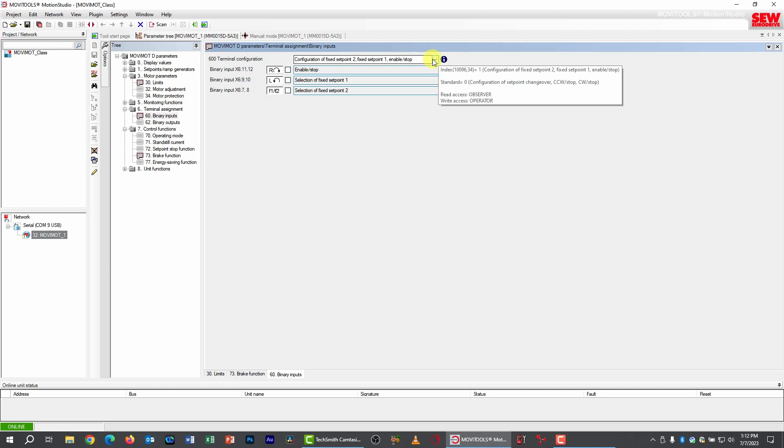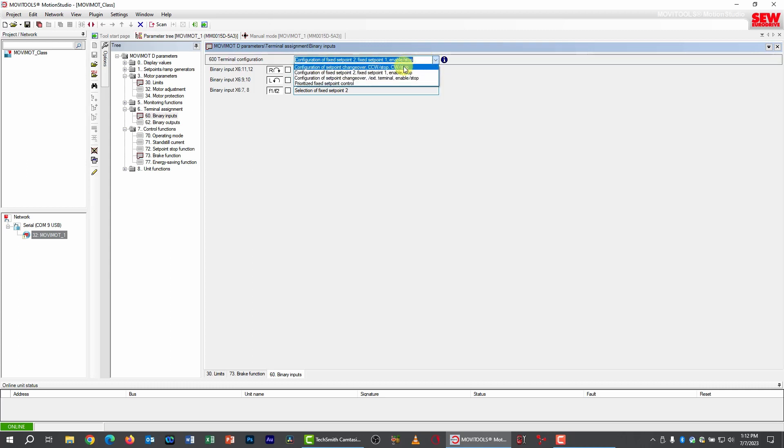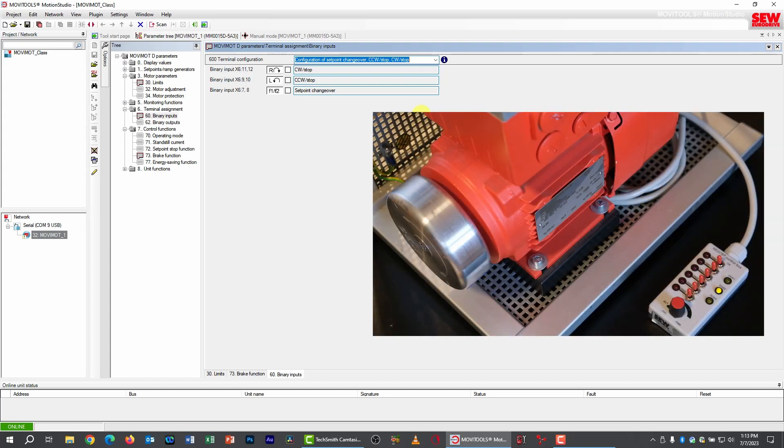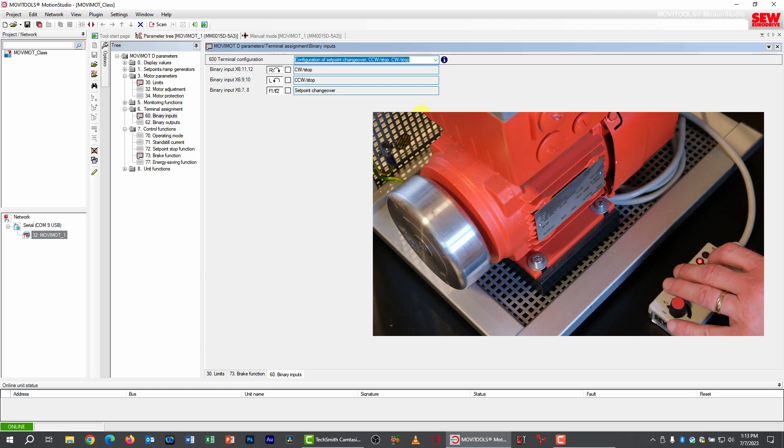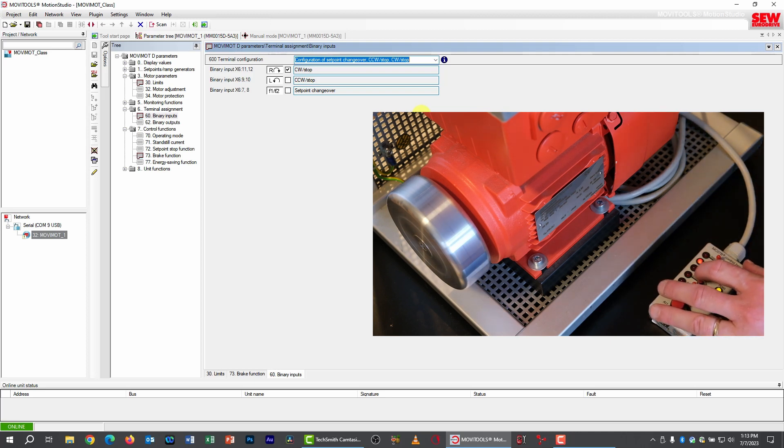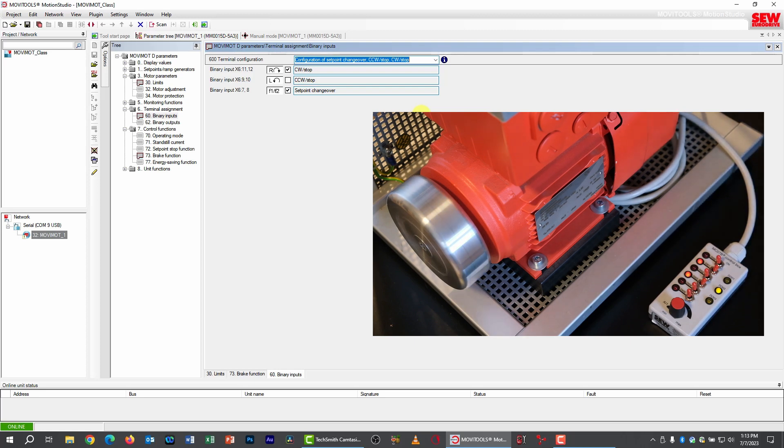And we need to go back to the standard binary mode where the drive is controlled by clockwise and counterclockwise and has the setpoint speed changeover selection. Now, right now, the motor is not turning because clockwise and counterclockwise are both turned off. When we have enabled the brake release function, the F1, F2 signal now has two purposes. When the motor is turning, the F1, F2 switch controls which setpoint is in force. Let me demonstrate that. I'll just start the motor up here. So we're operating at our F1 speed, which is controlled by a parameter in this case since we've disabled the mechanical controls. Now look what happens when I switch the F1, F2 switch on. We slow down to the other setpoint. This is normal binary behavior. We're very familiar with this.